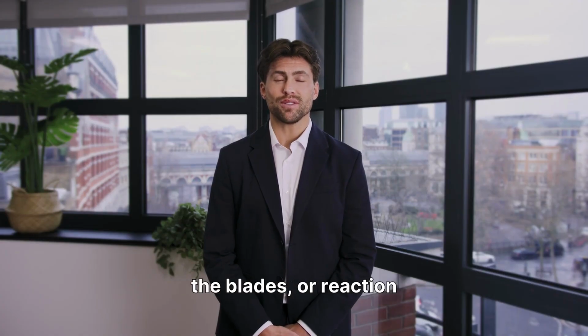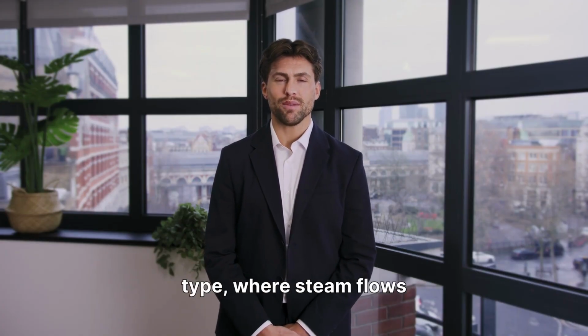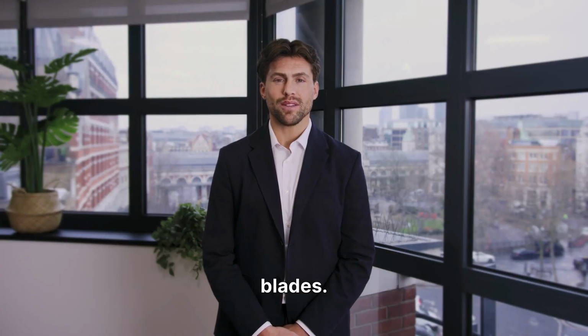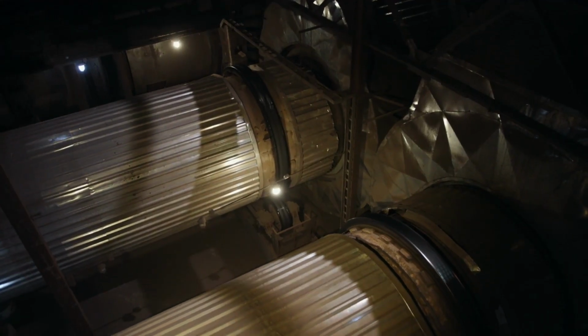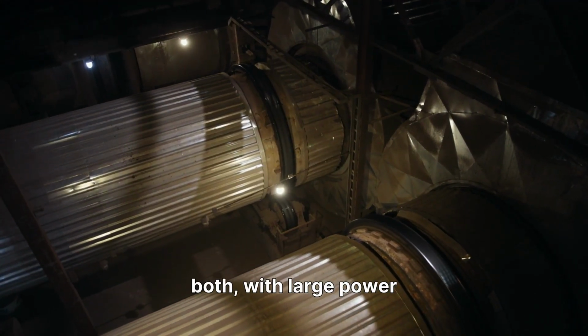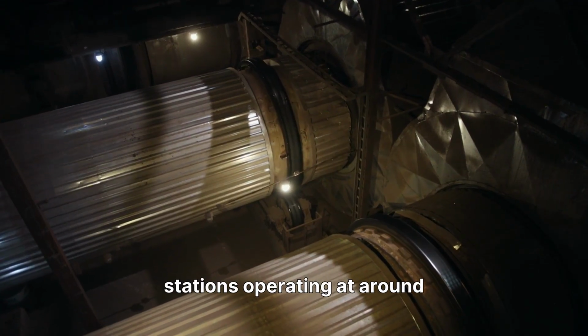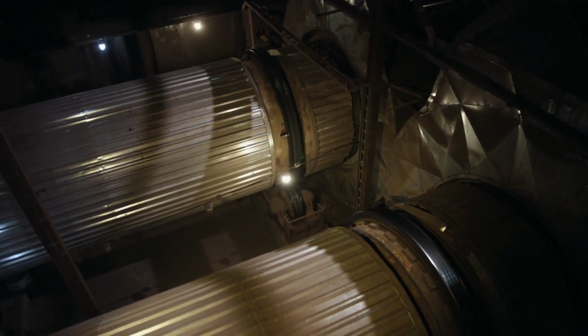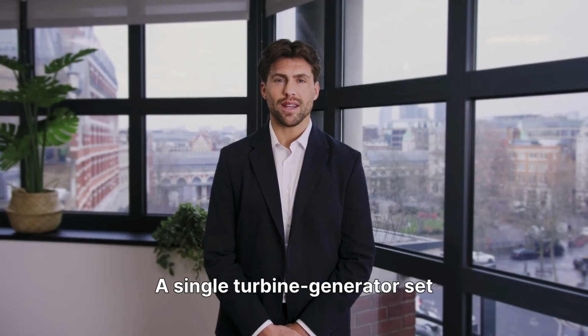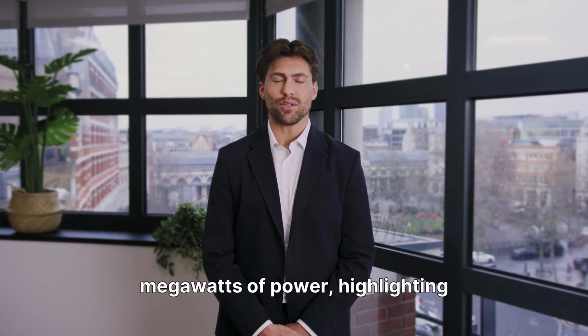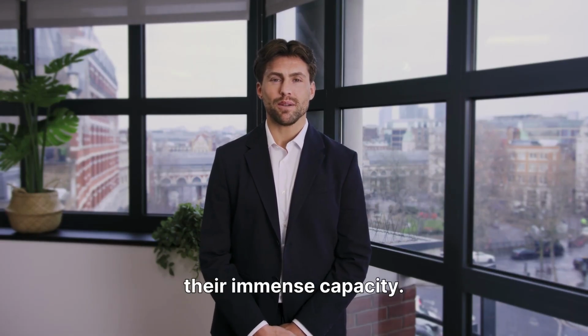Turbines can be impulse type, where steam strikes the blades, or reaction type, where steam flows and expands between the blades. Most modern power plants use a combination of both, with large power stations operating at around 3,000 revolutions per minute. A single turbine generator set can produce several hundred megawatts of power, highlighting their immense capacity.